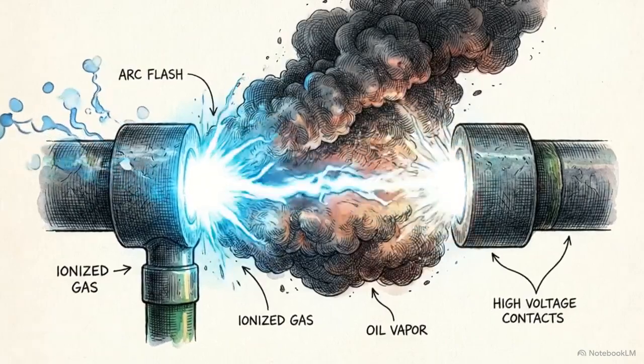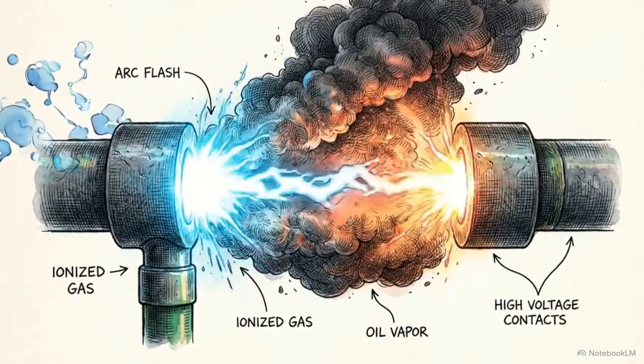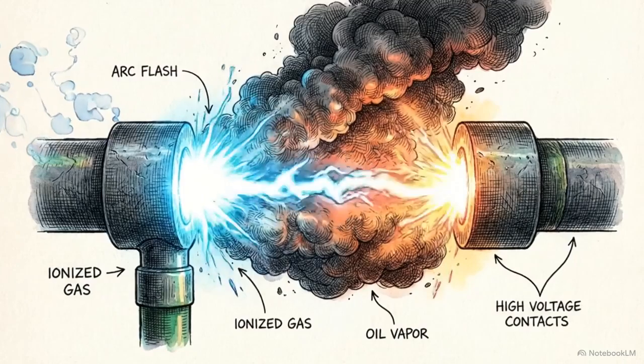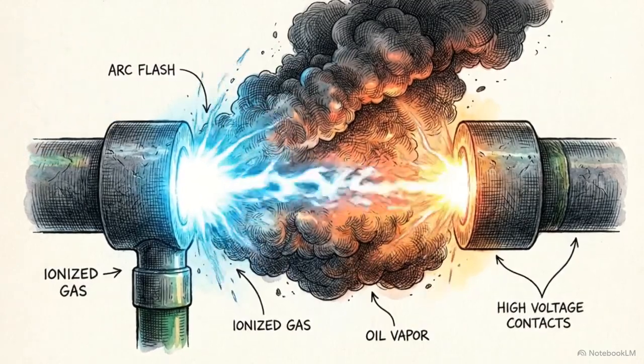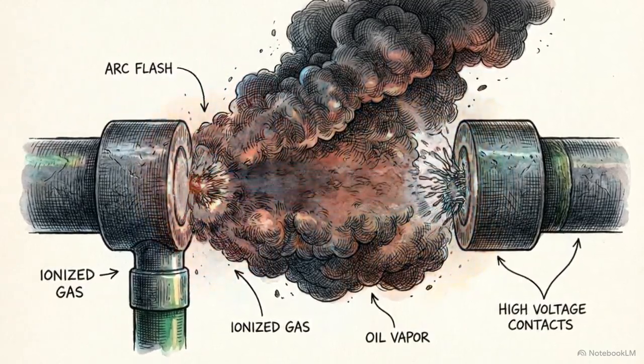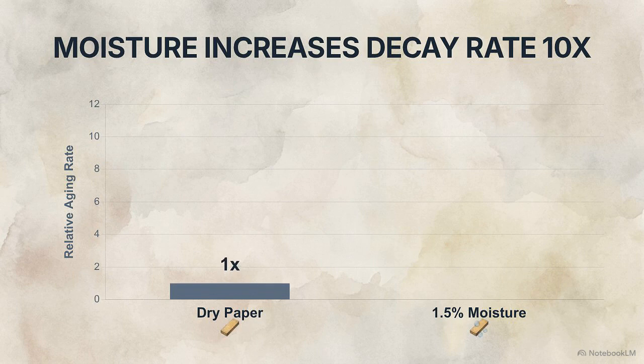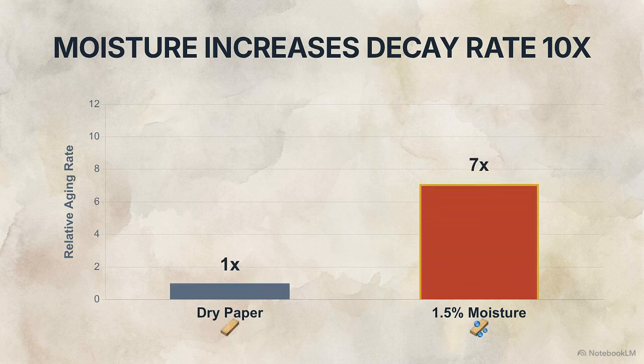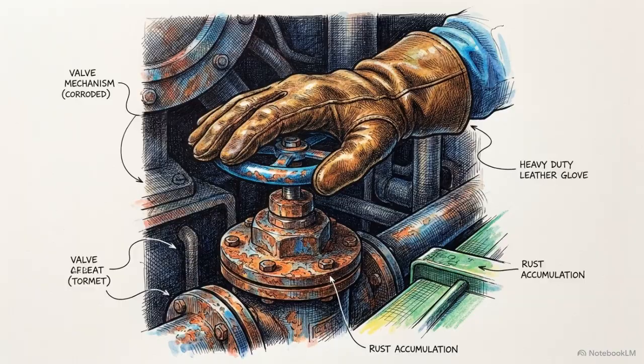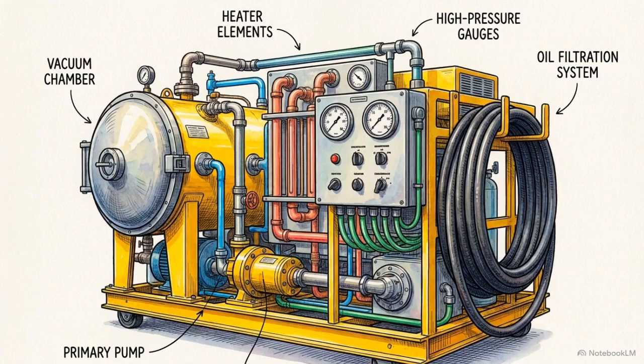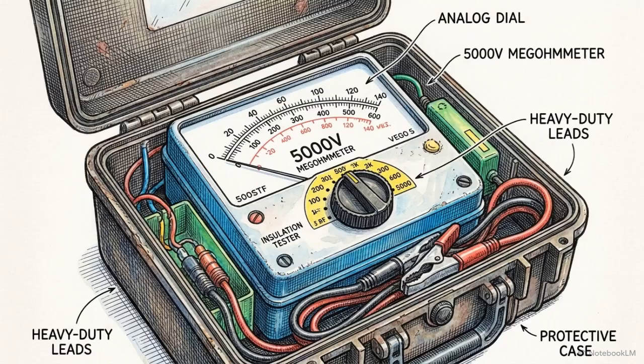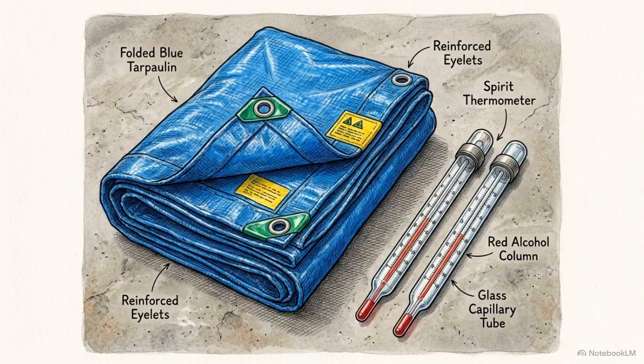When moisture gets trapped inside high-voltage electrical equipment, the result is often a sudden, catastrophic, and explosive failure. Paper insulation with just 1.5% moisture ages 10 times faster than dry paper, making water the primary driver of equipment decay. To neutralize this threat, you need a high-capacity filter machine, a 5,000-volt insulation tester, tarpaulins, and spirit-type thermometers.